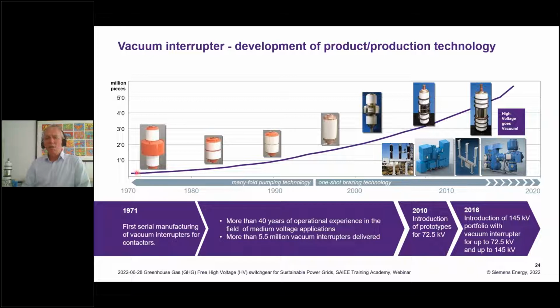Looking at the history of vacuum interrupters, you see medium voltage starting on the left, and then in the 2000s, it became a high voltage vacuum interrupter for 72.5 kV and for 145 kV. You see here the 72.5 kV - I don't know if you have it in the camera, but it's also standing behind me. This is a 72.5 kV vacuum interrupter, which is inside this live tank vacuum circuit breaker, or inside that GIS here.